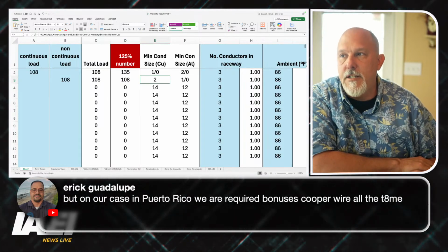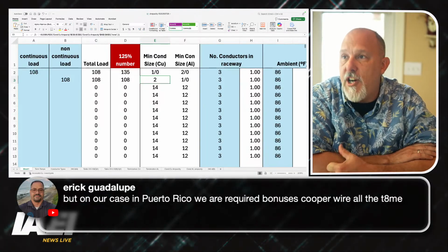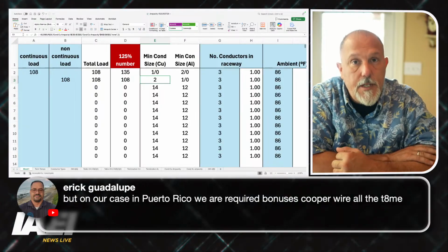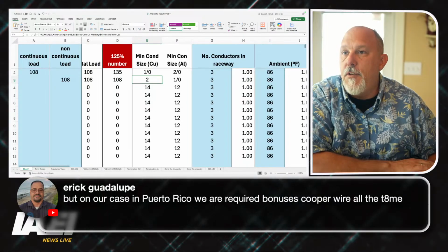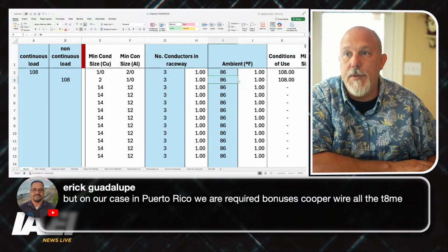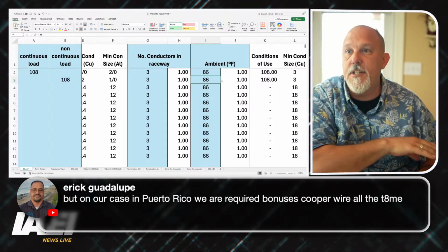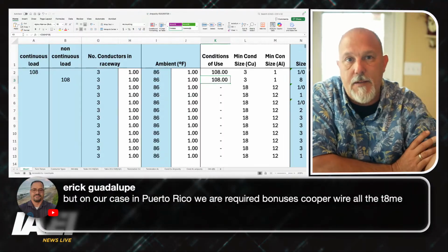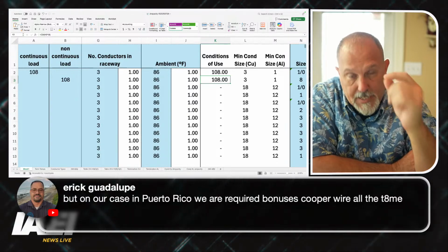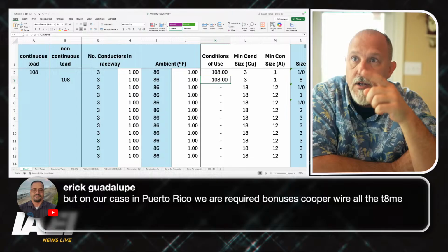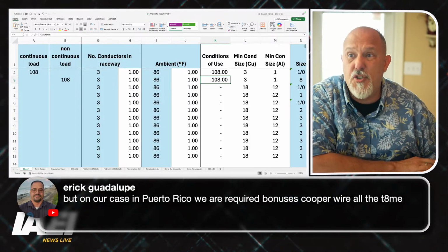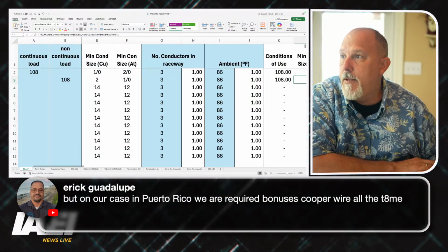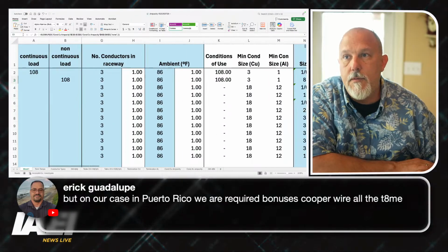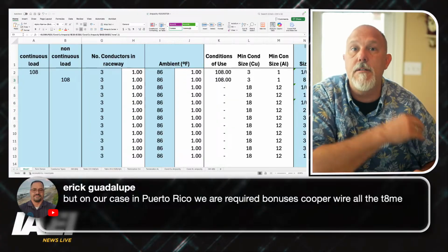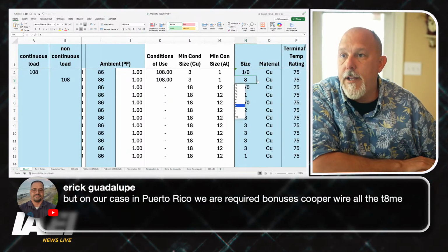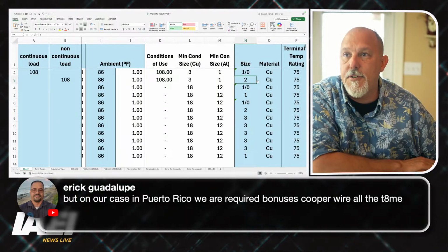My smallest conductor size is a 2 gauge for copper. My smallest conductor size for aluminum is a 1-aught. If I look at the conditions of use, I have 3 conductors in my raceway, 86 degrees Fahrenheit, so unity on conditions. That means, based on conditions of use, my conductor has to be able to handle 108 amps. I can pick a 3 gauge copper or a 1 gauge aluminum. So my choices in copper is a choice between 3 and a 2. The larger of the two is the 2 gauge because as the numbers get smaller, the conductor gets larger. So my size conductor is a 2 gauge.